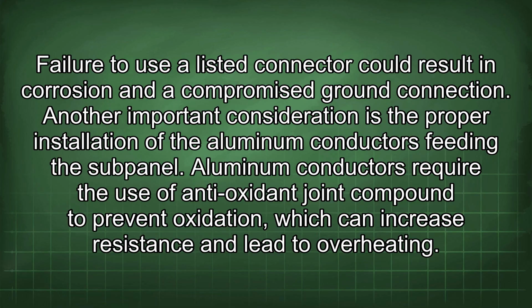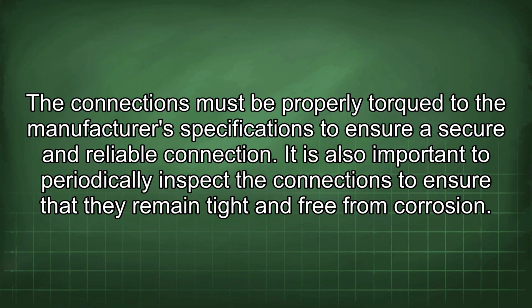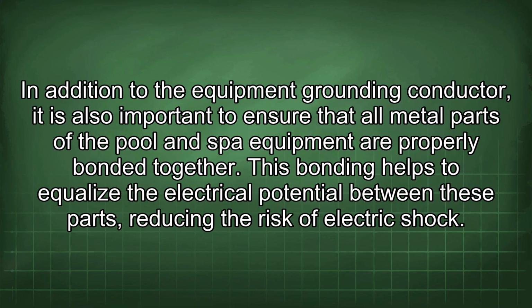Another important consideration is the proper installation of the aluminum conductors feeding the subpanel. Aluminum conductors require the use of antioxidant joint compound to prevent oxidation, which can increase resistance and lead to overheating. The connections must be properly torqued to the manufacturer's specifications to ensure a secure and reliable connection. It is also important to periodically inspect the connections to ensure that they remain tight and free from corrosion. In addition to the equipment grounding conductor, it is also important to ensure that all metal parts of the pool and spa equipment are properly bonded together. This bonding helps to equalize the electrical potential between these parts, reducing the risk of electric shock.